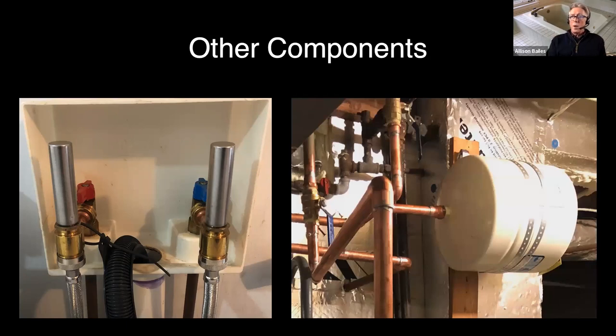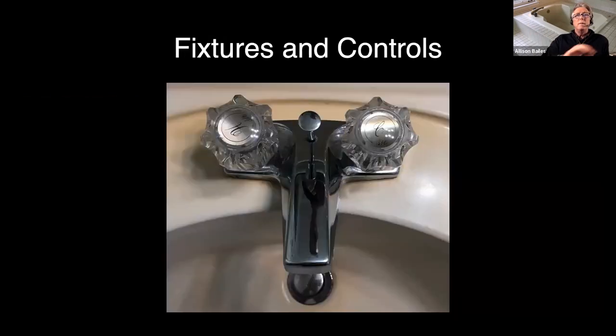Another important property of water to note is that it expands when it heats up. So when you have a water heater heating up cold water, that water expands. It used to be that there wasn't a check valve stopping that water from going back into the supply line at the street, but now those check valves exist, so it cannot expand back to the water supply. So we put these expansion tanks—little 2 or 3 gallon expansion tanks—there to deal with that expansion that happens as the water heats up.